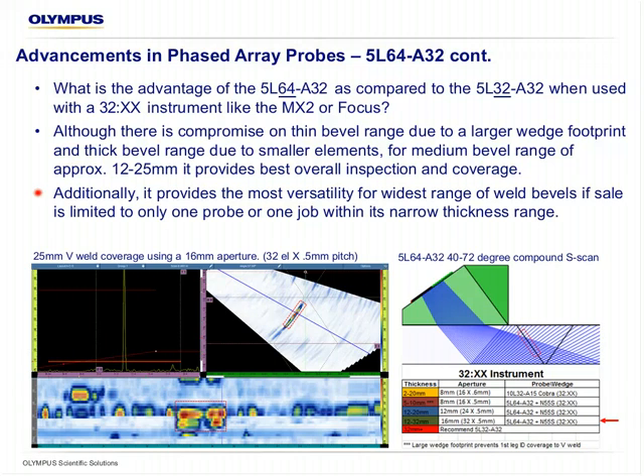And again, in this example of standard V-weld of 25 millimeters, we see the aperture chart telling us that a 16 millimeter aperture is appropriate for this thickness and weld bevel. That can be achieved either by a 32 times 0.5 millimeter 64 element A32 or from a 1 millimeter times 16 5L32A32 using the larger pitch.